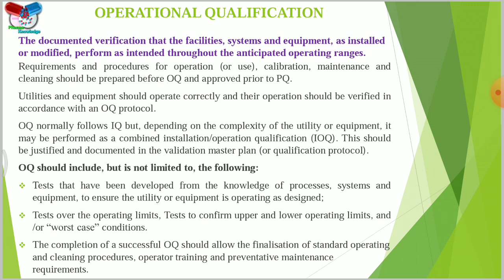During operational qualification, the training of operators for the utility and equipment should be provided and training records should be maintained, which is the minimum requirement. Calibration, cleaning, maintenance, training and related tests and results should be verified as acceptable. Deviations and non-conformances observed should be recorded, investigated and corrected or justified. The results for the verification of operation should be documented in the OQ report. The outcome of OQ should be recorded in the conclusion of the report, normally before PQ is started, which we have already discussed. Now we'll talk about the PQ.